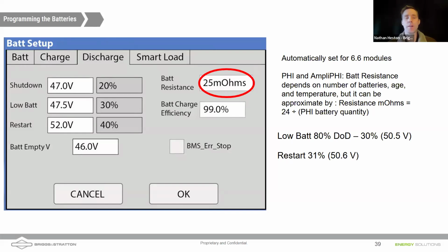The inverter's still there. And then if you've reached that, and then the sun comes out and the batteries start charging, it doesn't just immediately turn the loads back on. What does it do? We have to get up to that restart percentage or restart voltage before it will turn loads back on. And that's to give the batteries a chance to charge up. Generally speaking, if the solar wasn't strong enough to power loads, then those batteries would just be discharging. And so to prevent a back and forth cycle, we normally recommend going 10% above your low battery. So let's keep going.